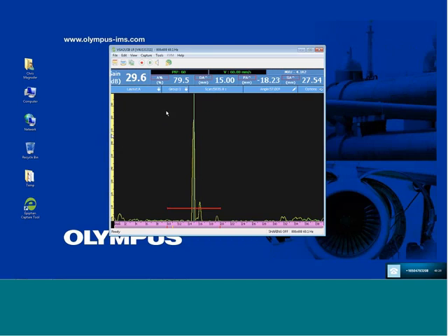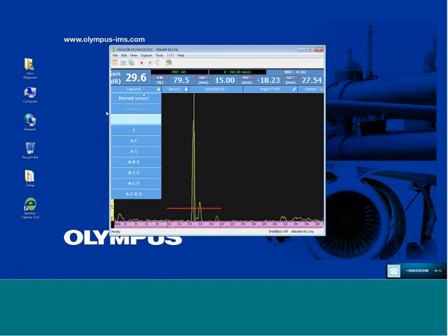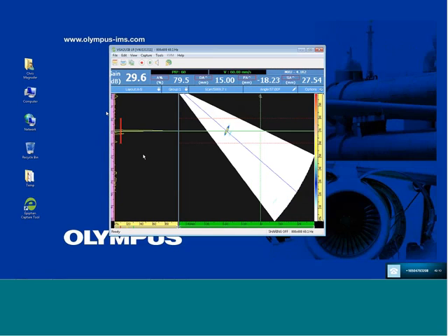Of the techniques that we looked at under our setup wizard that we see here, these are based on the option you selected for either phased array or conventional UT or conventional UT through the PA connector. The option that I select here, and I would see TOFD for a UT selection, would enable many defaults throughout the software, such as C-scan, readings, gate mode, and reports to be associated with that particular application technique.